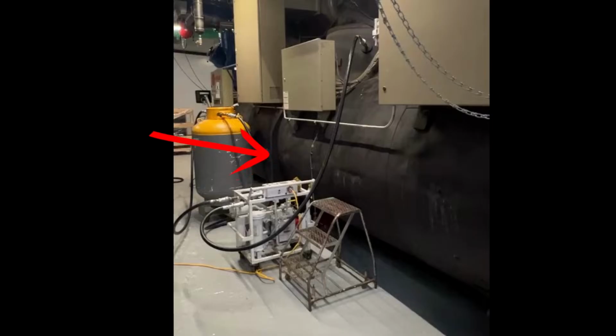Either way, getting back to how this process is working. So we open this valve. We're going to have some form of refrigerant flow in on its own by opening the liquid valve. So we're coming in off of the bottom of the evaporator into the liquid valve of this tank. And then out of the vapor side of this tank, we're coming back into the inlet port of our recovery machine. So that's coming in here. We're going to flow through the recovery machine, back out of the outlet port, and push that vapor back into, in this particular case, the suction elbow of the chiller.